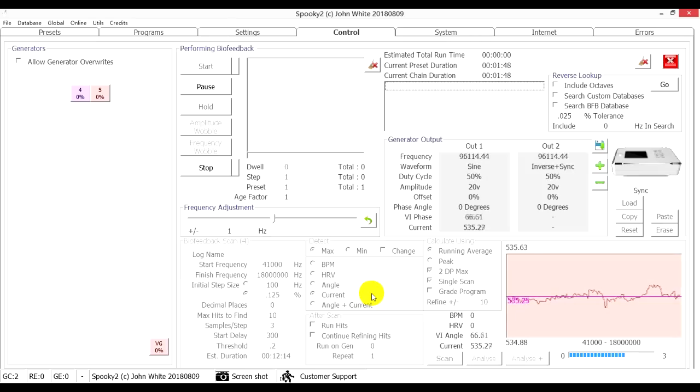The second way is phase angle. If you are walking with a child, normally they are at your side. But if you start walking over rough terrain, the child will fall behind. Phase angle is like the distance between yourself and your child. The terrain is everything between the TENS pads, and Generator X measures when the terrain is rough or smooth.